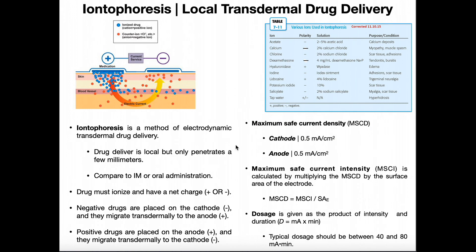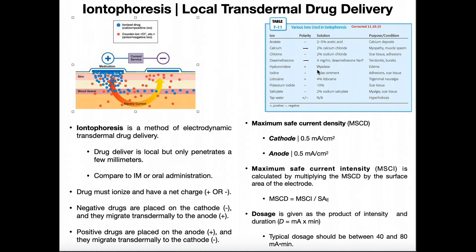An important point before looking at setup parameters: whatever electrode you put the drug on, that electrode becomes the active electrode. In this example, since the drug was positively charged it was placed on the anode, so the anode is the active electrode and by default the other one is the dispersive electrode. However, if we were dealing with dexamethasone — which has a negative charge — we would put it on the cathode, and then the cathode would become the active electrode, while the anode would be the dispersive electrode.